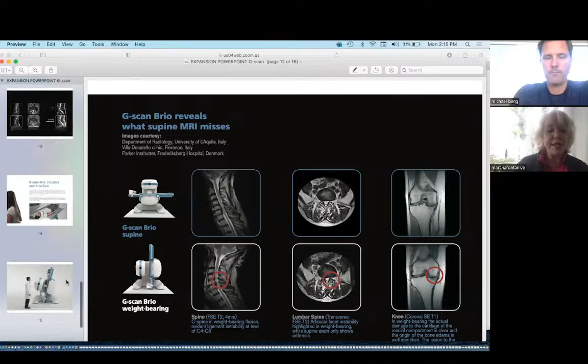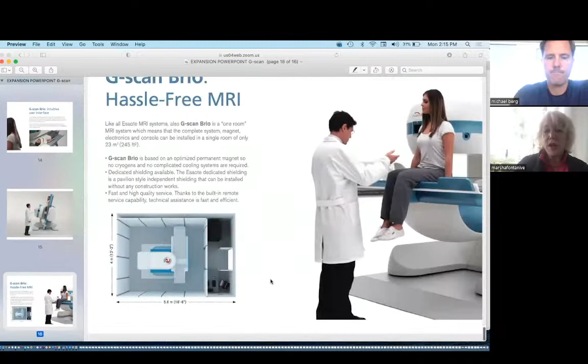But this machine has, I wanted to show you, self-shielding right here. They can buy the shielding. It's around $100,000. It's a snap-on shielding system. A normal build out will be about $250,000. We're coming in at around $100,000, and you could put wallpaper on it, decorate it any way you want. It just snaps in. Most of these physicians that buy these machines have to do a build out on floor reinforcement only, so it's very simple. Snap in, and as you can see right here is your area for your controls and your computer.